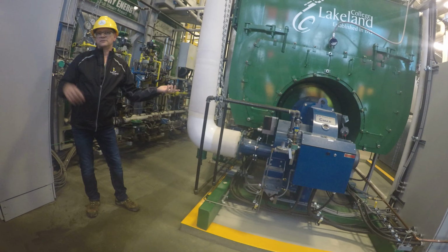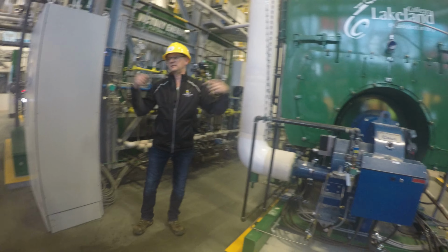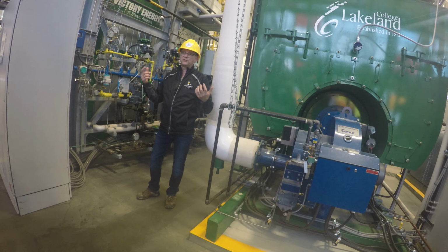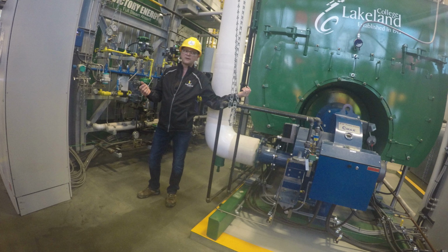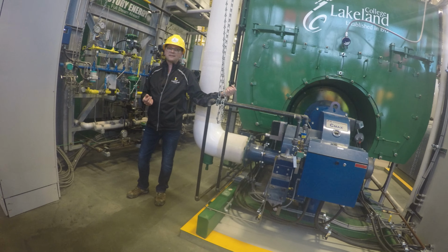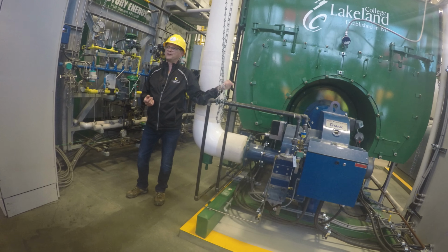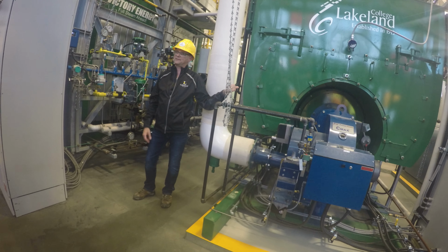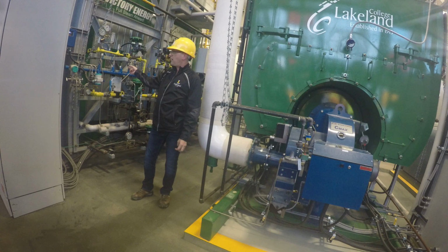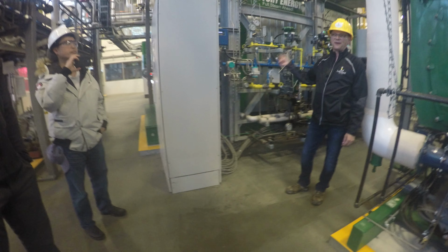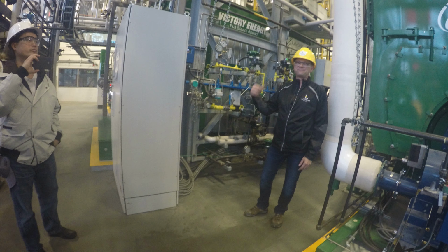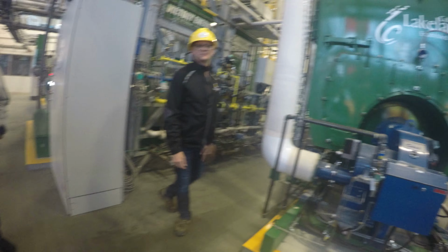The difference between a fire tube and a water tube, this thing has twice the water in it than this. So this has about 2,500 gallons, this is about 1,200 gallons. The fire tube is like a good old workhorse. Takes a little while to get her going, but once you get her going, she's just steady, and you can pull steam out of here and she'll just keep up, like pulling on the old harness. A water tube is like a thoroughbred racehorse. Quick to go, but not so good over the long distance. It'll peter out of steam where this thing will take over.